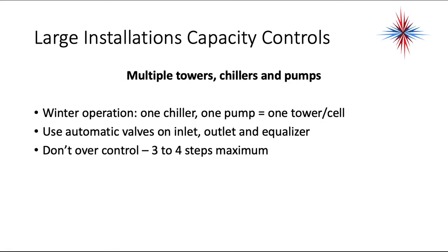When you have multiple towers, chillers, and pumps for winter operation: one chiller, one pump equals one tower or cell. Use automatic valves on the inlets, outlets, and equalizers. Don't over-control — three to four steps at a maximum, and then you have to stop, wait, and see what happens.